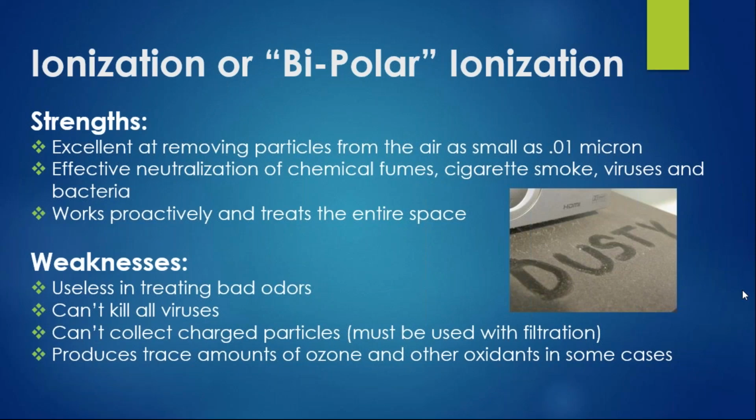Weaknesses: they're useless in treating odors. If you have stinky odors in any particular application, I wouldn't go bipolar ionization. It's not going to do anything for odors. It won't kill all viruses. And if you think about what we just said, it's going to make those particles precipitate out of the air. There's no means to collect that, so you have to use it in conjunction with filtration. Some ionizers, you have to be careful because of the level of electricity that they use, they can actually create a small amount of ozone. And ozone we don't want in our breathing air because it's an irritant to us as humans. We don't want to go there.